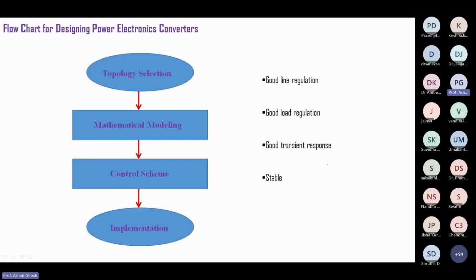Now you want to discharge the battery. The battery is connected to the DC bus, and you want to discharge it from 12 volts to 48 volts. Practically, is it possible to directly connect the battery to the 48 volt bus? No, it's not possible. So what you need to do is connect the battery through a power electronics converter to the DC bus.